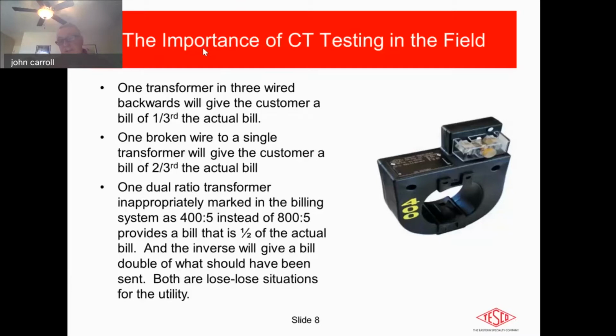I always try to encourage anybody, when they go to a site, to use a camera phone. Everyone has one these days, and they're really good. They're high definition. You don't have to get too close to the meter itself, or too close to the circuit, but you can zoom with your camera and get a really nice close-up of that nameplate. And that nameplate will tell you a whole number of factors under which the accuracy of that CT will be determined. Make a note of it and make sure that the other two in the circuit, so there are three of them, are the same. I have seen instances where they are not. Don't take it as read that what's on there is actually correct until you've checked it.